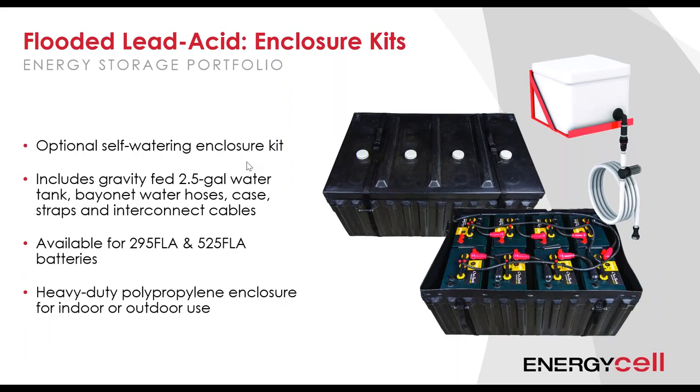I also wanted to talk about the kit options that we offer for the FLAs. When you buy FLA batteries, they come as is. There are no interconnects or watering systems or racks or tubs or anything. But we do sell this additional self-watering enclosure kit that comes with a 2.5-gallon water tank, bayonet water hoses, case, straps, and interconnect cables. All comes in one kit. All you have to do is make the connections and mount the tank, and it's pretty much good to go. It's a turnkey solution for folks that want to save a few bucks and don't like the idea of maintaining the battery. This system will extend those maintenance-free cycles.